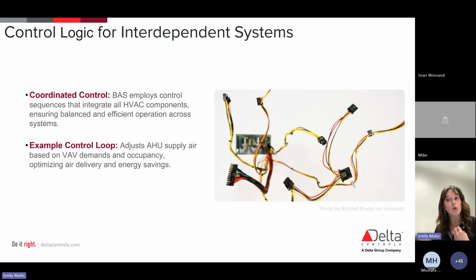And then that typical control loop is going to involve three key components that we talked about. That first one is going to be your sensors. That's going to be what's measuring your current condition inside of your zones. So again, your room temperature, your occupancy. It's then going to have a controller. That controller is what's going to compare our sensor input to a predefined set point. So it's actually comparing what you have in the building to your set point.